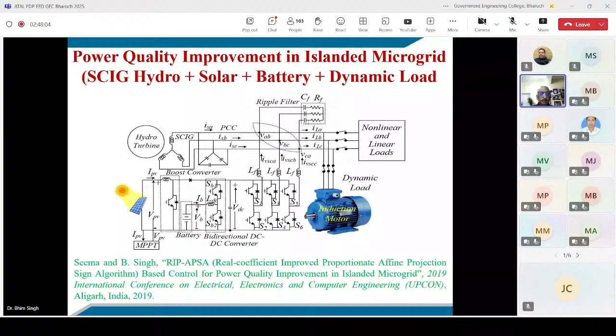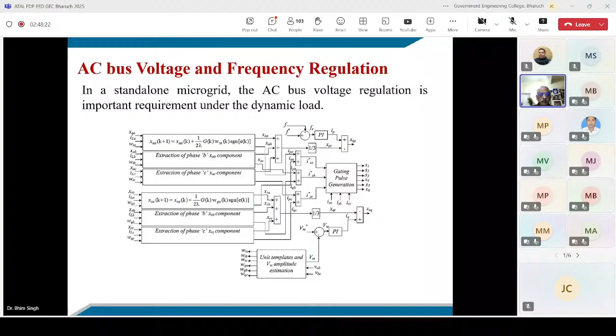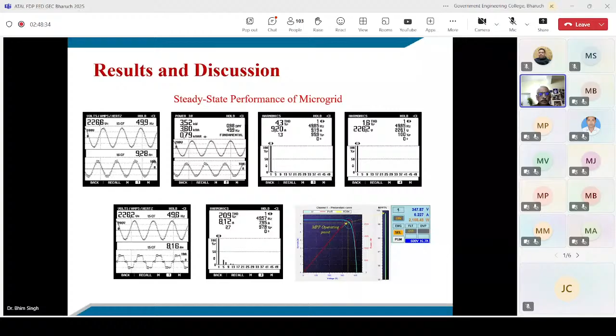This was the control, with regulation of voltage and frequency. They used a kind of nonlinear, adaptive control for voltage and frequency control of this system, because it is a DC link voltage control from the battery. We were able to operate satisfactorily with only a very low THD of 1.6%, in spite of a nonlinear load having THD of 21%, without much problem under varying load and varying situations.